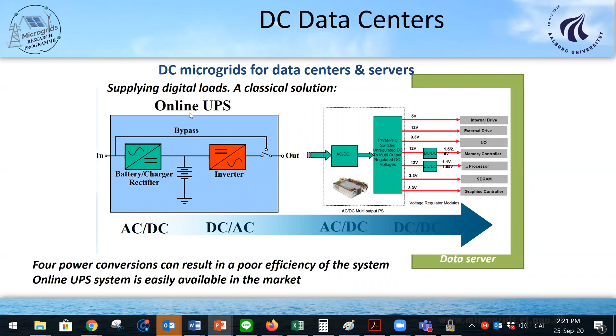This is another example I like to talk about: increasing efficiency by reducing the number of stages. This was for a data center. Normally we have a lot of data centers moving to DC, and in this data center we need a number of voltages. Normally when you go off the shelf, you just try to find a UPS system - in that case, an online UPS system to support the front end.